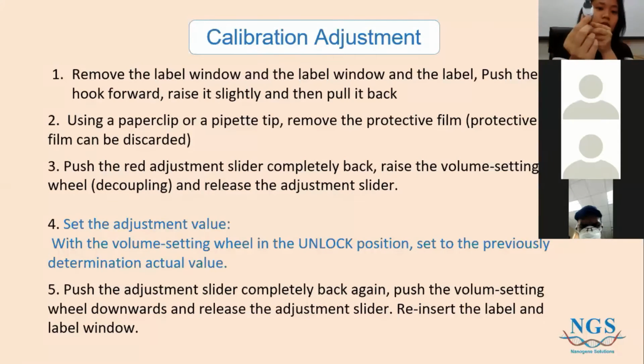So here, for my pipette, I would just need to pop up this label window, and there will be a red slider. I would just need to slide it back, and then it will unlock this operating knob right here. And once you unlock the knob, you can actually turn it clockwise or anti-clockwise to adjust your values. All right, so it's very simple. Some pipettes are simpler than others, but always, like I said, if you need to calibrate it, if you don't have time to check it, there are professionals who will do it for you, and usually it doesn't take too much time for them. All right.